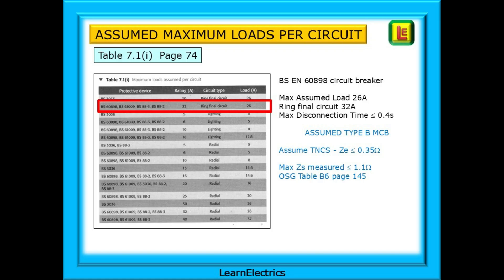In a domestic scenario, not every socket will be in use at the same time and not all equipment will be on at the same time. The breaker we've decided will be a Type B with a disconnection time of not more than 0.4 seconds. ZE for the circuit will be 0.35 ohms maximum, and ZS should not be more than 1.1 ohms when measured on site with a test meter. Do note, Table 7.1.1 shows the breaker as BS60898 when in fact it should say BSEN60898, but we knew that.